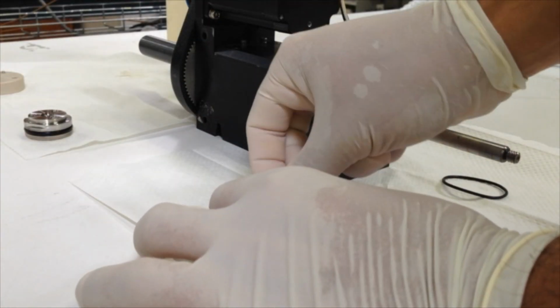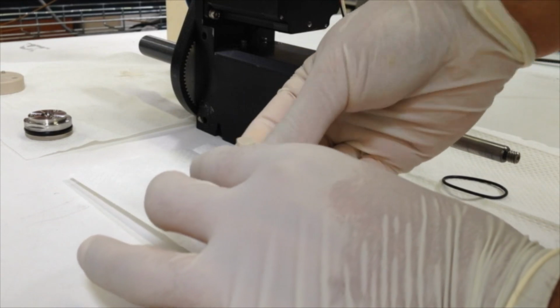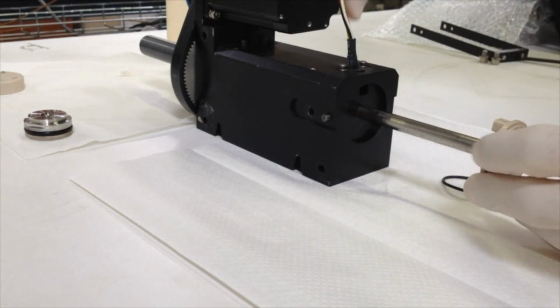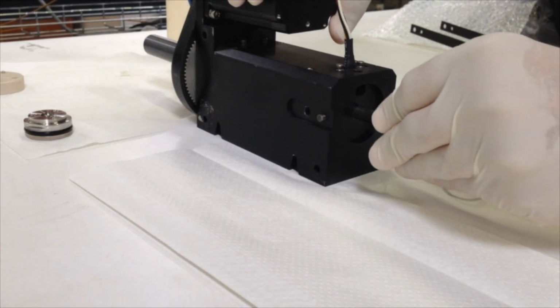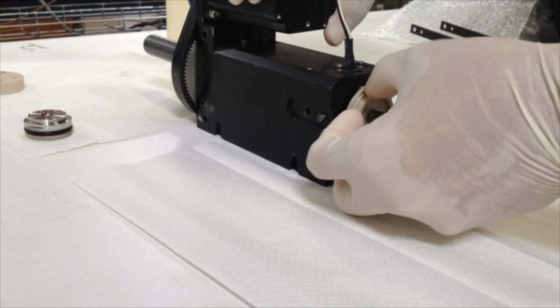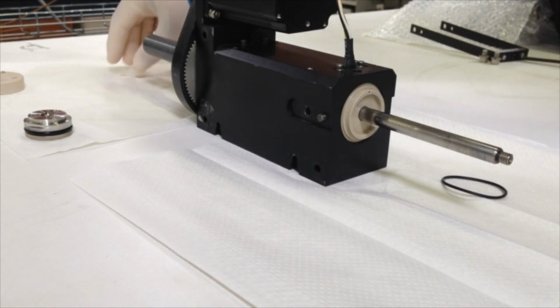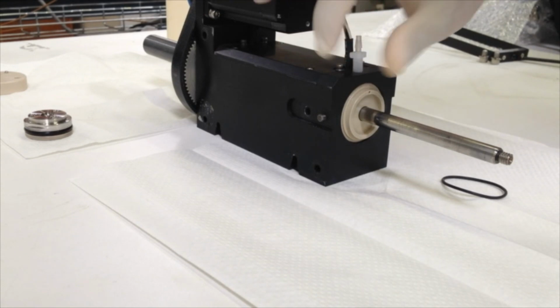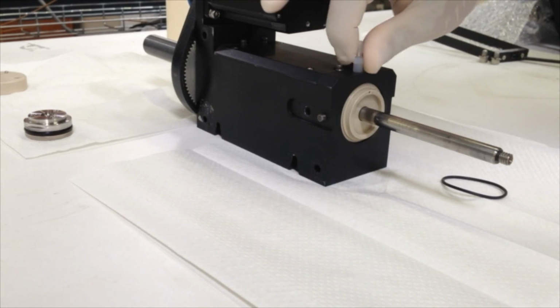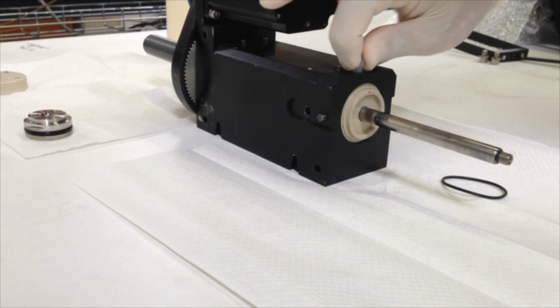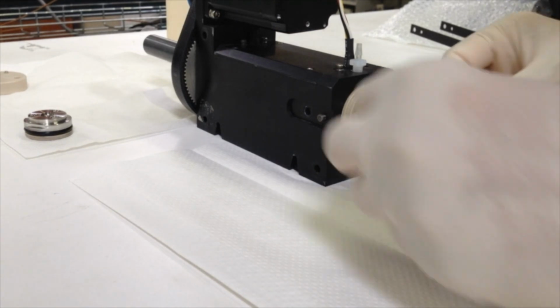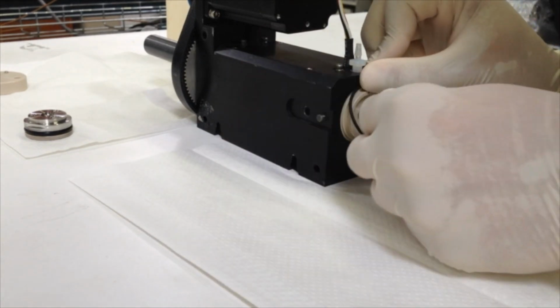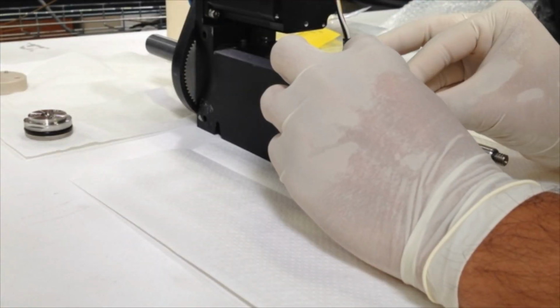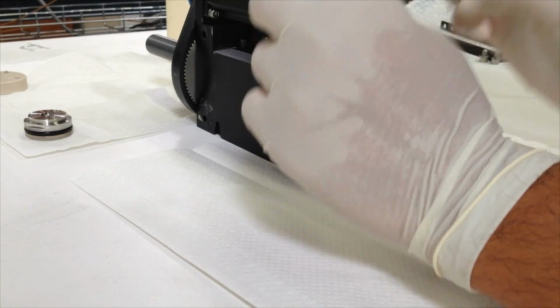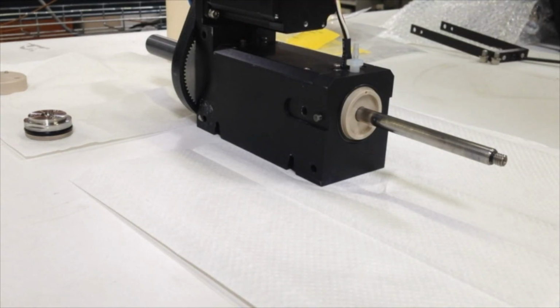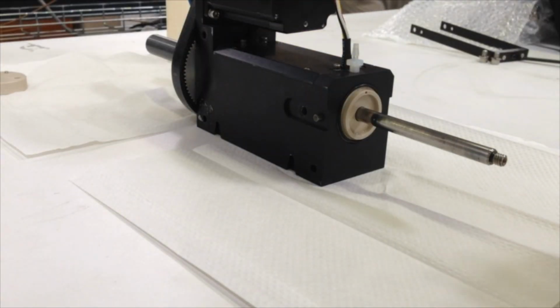Place the clean piston rod O-ring into the piston O-ring guide. Lubricate the piston rod O-ring with some methanol and then slide the piston O-ring guide onto the lead screw all the way into the pump body. Screw in the piston wash connector to lock the piston O-ring guide in place. Now place the secondary cylinder O-ring into the groove of the piston O-ring guide. Screw on the newly assembled piston head.